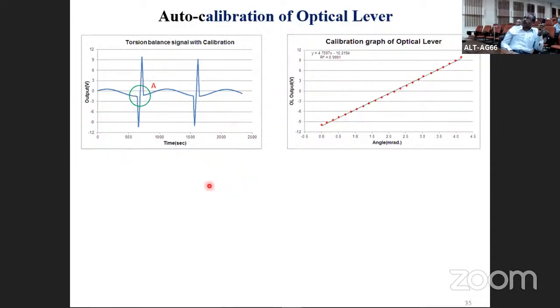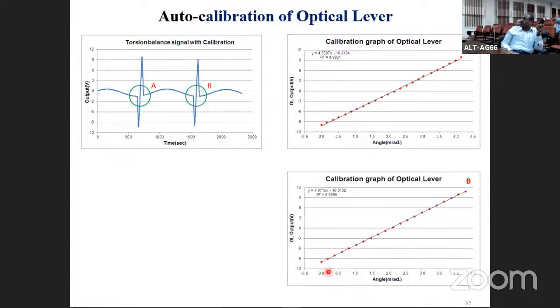What happens if you do it just before the turnaround time? And that's what is being shown here. Now you see all the points lying on the line. The R-square value itself tells, and the calibration value is almost 2 to 3% more compared to this. So it's always good to invoke the calibration just before the turnaround, so that you maintain at a really very flat portion of the turnaround and not at the rising edge. This contributes to the error.